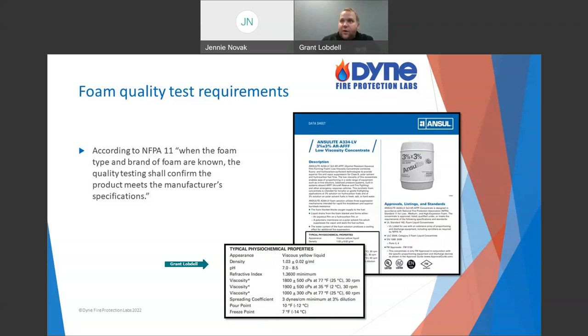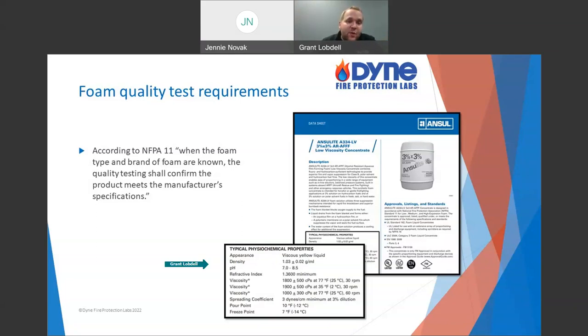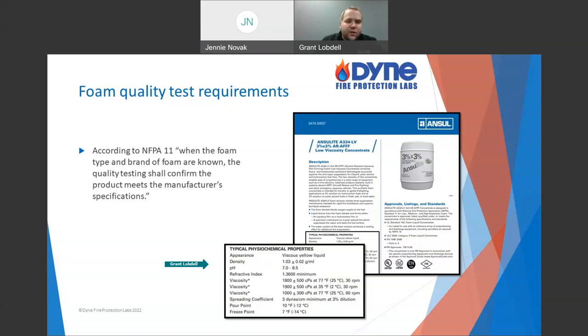If the product isn't known, it doesn't mean you can't test it — but you're almost shooting yourself in the foot. We have to assume the worst and require a certain minimum level of performance. It's always best to know what you have and get us that product information so we can make the correct comparison. If you really don't know, you can still send it to us; we have some minimum benchmarks we're comfortable saying is acceptable. In that case, we look to other standards — like the MIL-Spec, which has a 5.0 expansion minimum across the board. We allow a 10% degradation from that for field samples.